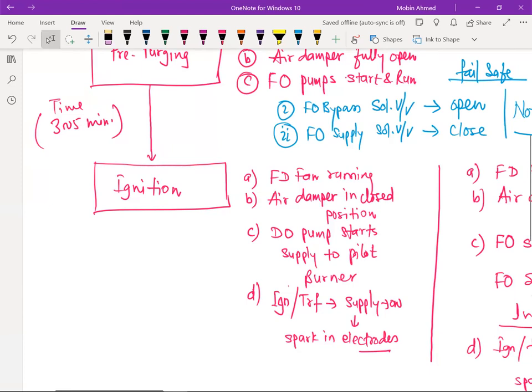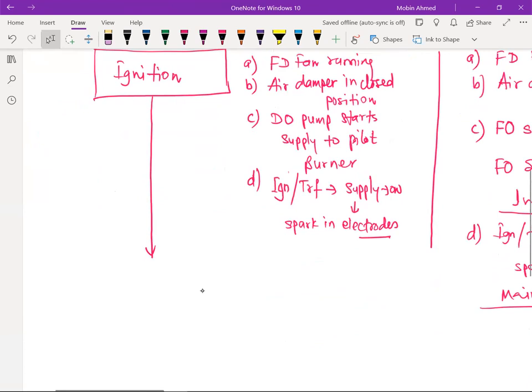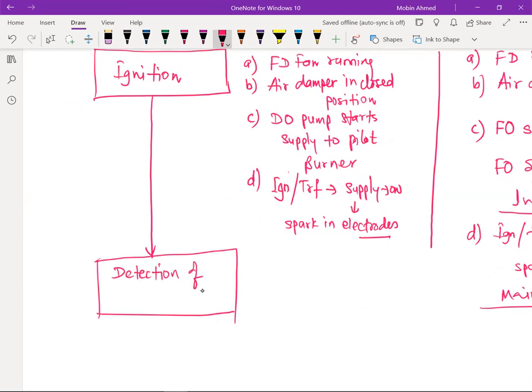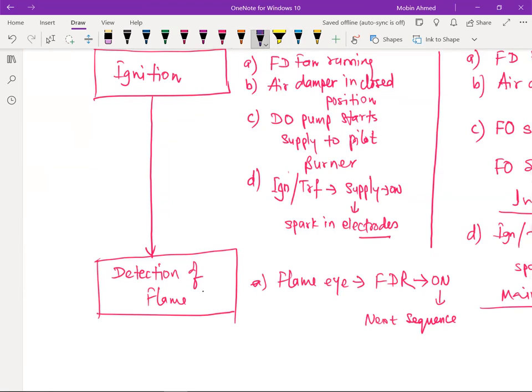Okay. Now next is after this ignition. So ignition takes place, then there will be the detection of flame. So next is the detection of flame. Detection of flame is done by the flame eye. Correct? So the flame eye is going to detect the flame. Flame eye is going to send the signal to the flame detection relay, FDR. Okay, and once the FDR is on, then the next sequence will start. If the flame is not there, in that case, you are going to get an ignition failure alarm.